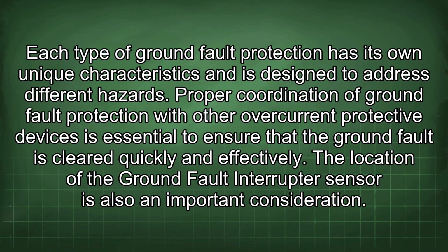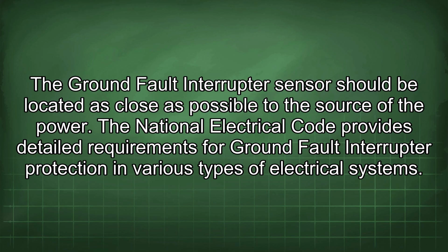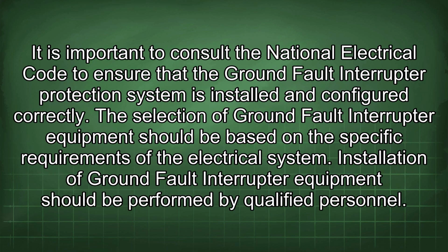Proper coordination of ground fault protection with other overcurrent protective devices is essential to ensure that the ground fault is cleared quickly and effectively. The location of the ground fault interrupter sensor is also an important consideration. The ground fault interrupter sensor should be located as close as possible to the source of the power. The National Electrical Code provides detailed requirements for ground fault interrupter protection in various types of electrical systems. It is important to consult the National Electrical Code to ensure that the ground fault interrupter protection system is installed and configured correctly.